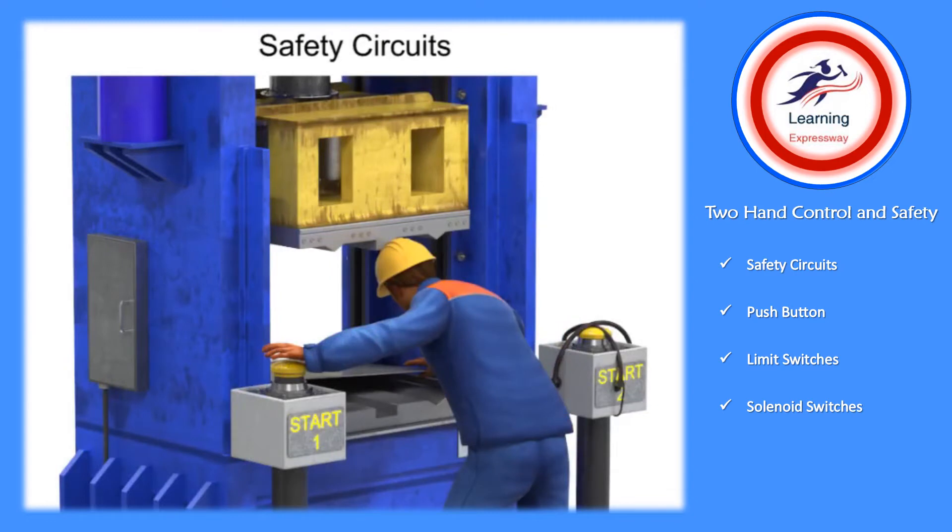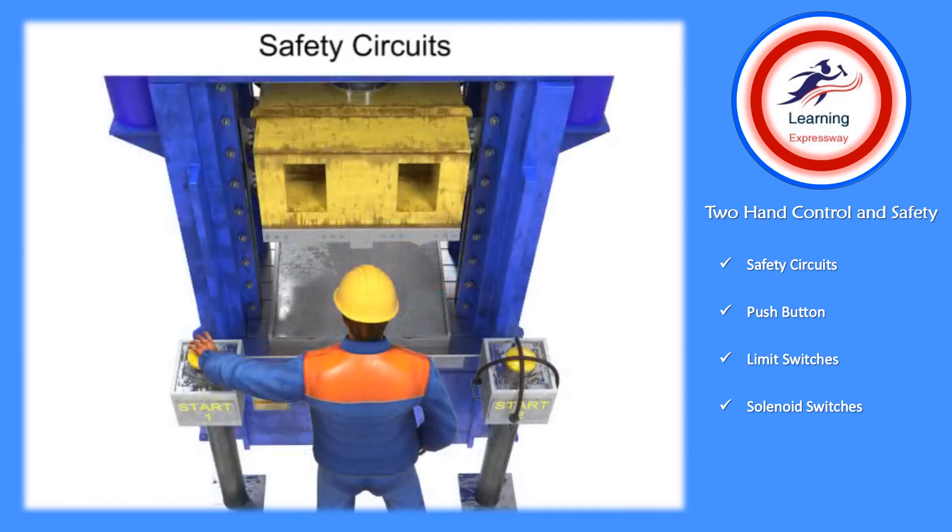To prevent this unsafe condition but still permit a single operator, anti-tie-down circuits are employed. An anti-tie-down circuit requires that the operator actuate both individual controls at the same time. If either control is prematurely actuated or continuously tied down, the cycle will not operate.